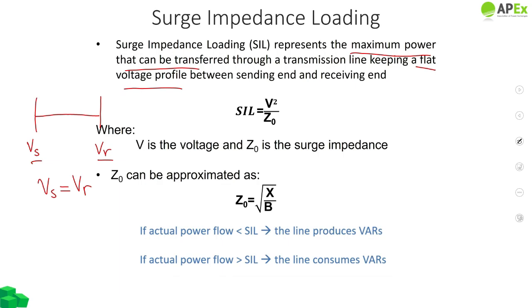So what is the formula for surge impedance loading? It's given by the square of voltage divided by something called the surge impedance, Z naught, which can be approximated by the formula given in the slide: Z naught equals the square root of the reactive inductance divided by the susceptance.